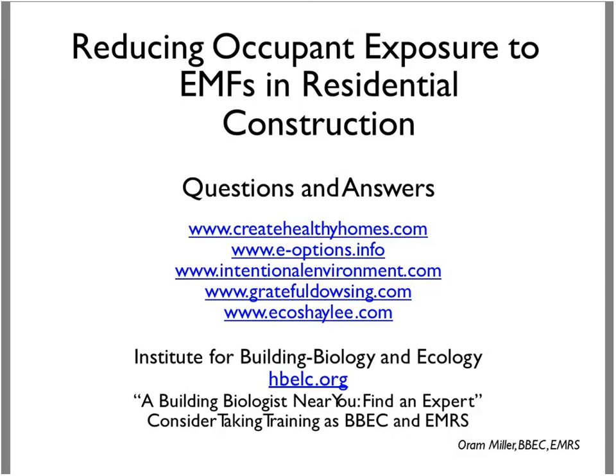So in the daytime, you can tolerate the Romex, it really comes down to these issues. But for electric fields, that's what you'd use metal clad wiring for. If you can afford it, flex is a better choice - you can run new wiring through it, you can't drive a nail through it like you can with NM or Romex wiring, and it sustains earthquakes better. So there are many advantages to metal clad wiring.